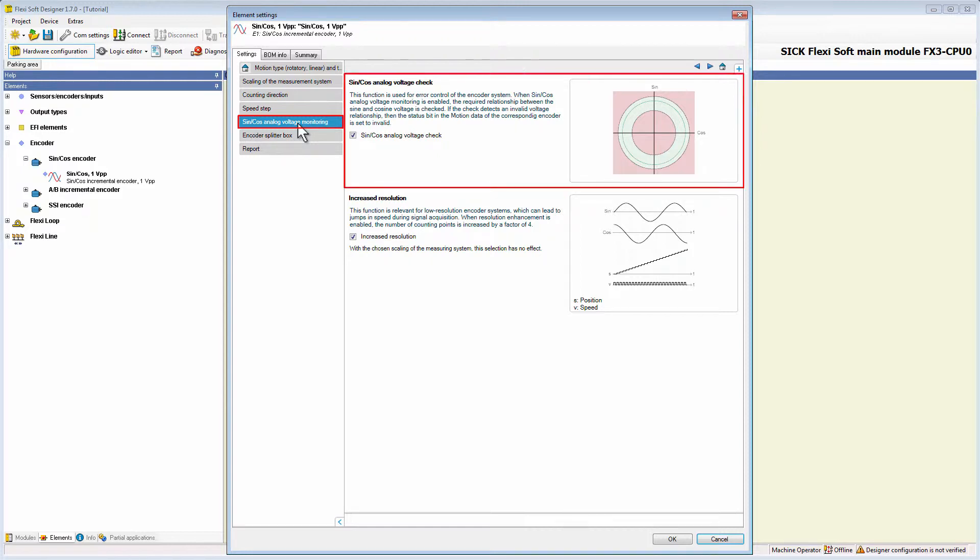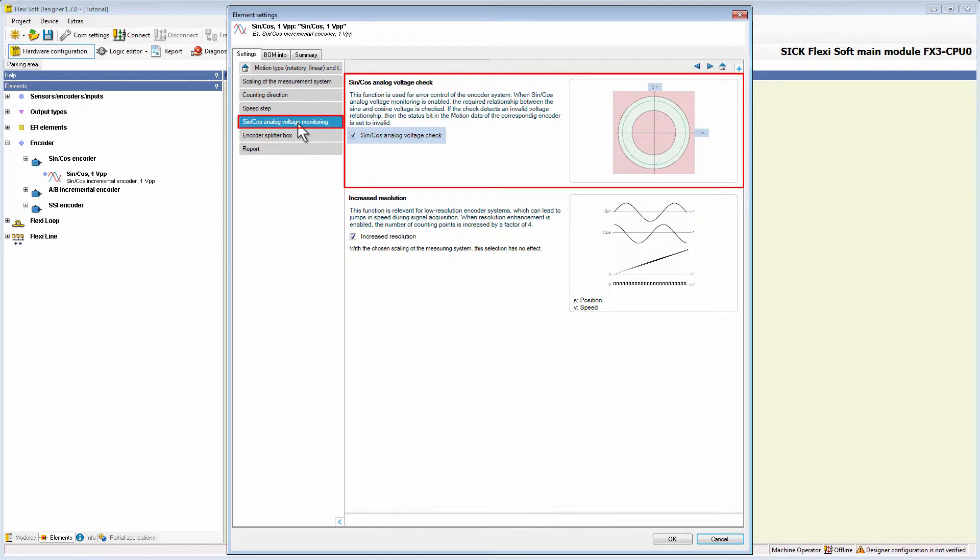At the top of this tab we have the option to check the sine cos analog voltage. If the sine cos analog voltage check is enabled, the required relation between the sine and cosine voltage will be checked. This option increases the diagnostic coverage because if the check detects an invalid voltage relation, the status bit in the motion data of the corresponding encoder will be set to invalid.